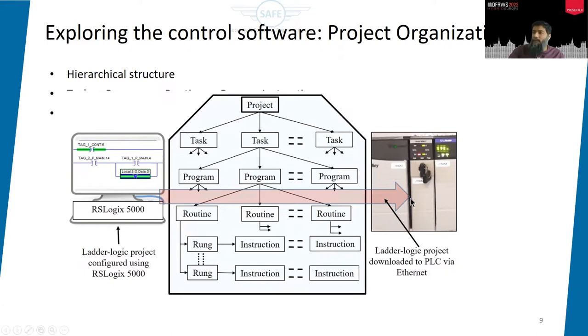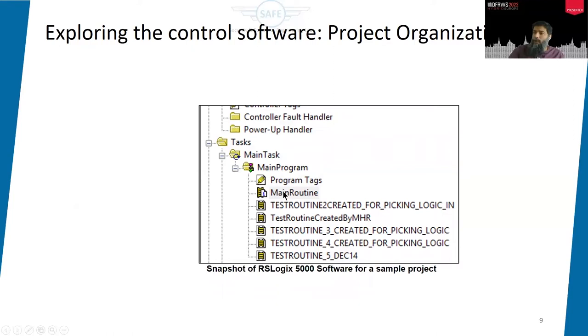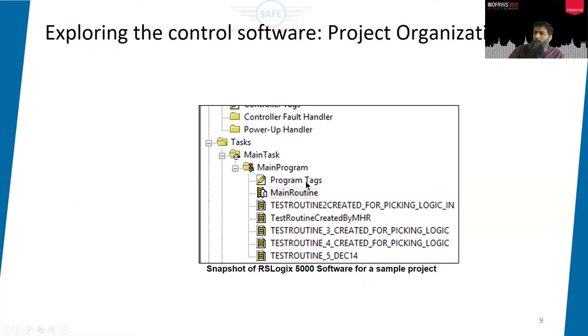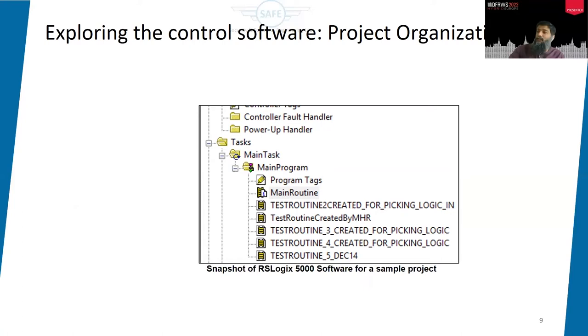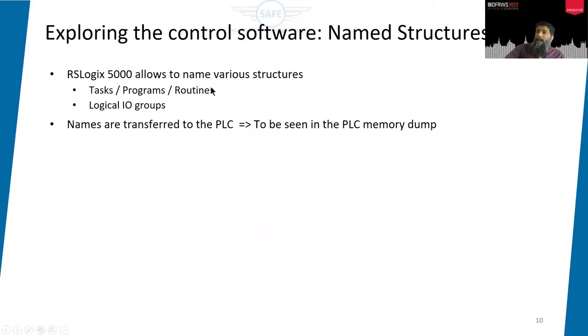This is a snapshot: the main task containing the main program, within which there are many routines. I have named some of the routines, as per the evaluation, to see them in the memory dump. Another important element is program tags — these are tags that can be used as logical inputs and logical outputs, similar to local variables in software programming. RSLogix 5000 allows us to name tasks, programs, routines, and logical groups, and these names are transferred to the PLC, so we can see them in the memory dump.